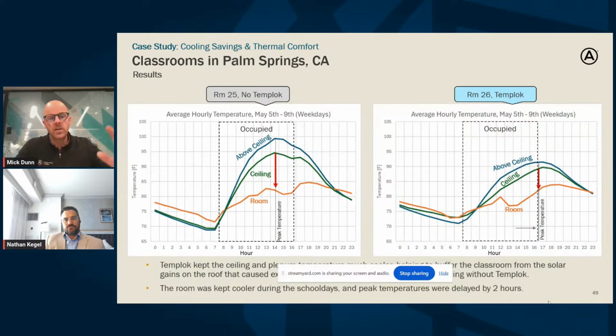And so when we're looking at the ceiling profile itself, up above the ceiling in that plenum, again, these are portable classrooms exposed with like metal roofing and fiberglass insulation, a lot of thermal bridging, a lot of thermal pressure on those structures. So it's getting up to 100 degrees in the plenum. And then the backside of that ceiling is the green line there. So the backside of the ceiling tile is getting up to 95 degrees in that environment. And below that ceiling, at the ceiling level, that room temperature is exceeding 80 degrees by about 10 or 11 in the morning. And that's what you're seeing at the bottom left of screen there. And it stays above that 80-degree temperature for most of the day, which is making it all the more difficult to maintain 74 degrees at the human comfort level.